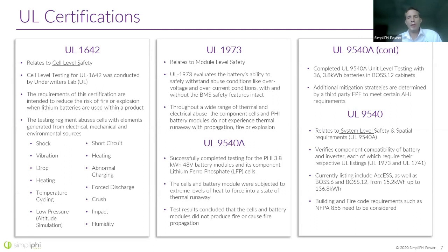Then there's a UL 9540A test. I want to emphasize that UL 1642, UL 1973, and UL 9540 are certifications - 9540A is just a test. The test is designed to look at batteries, purposefully create a fire in the battery, and see how the battery responds, in order to know what requirements will be surrounding the 9540 certification.